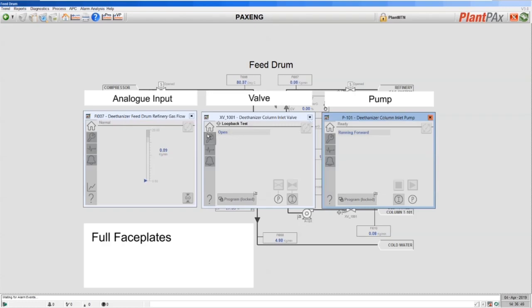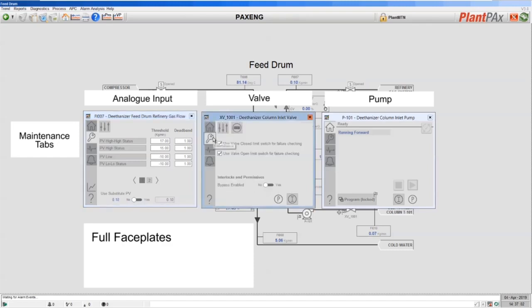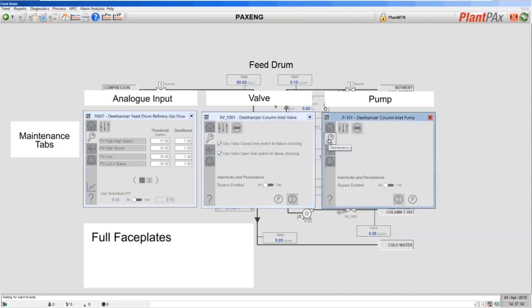The philosophy of the design for the full faceplates is that there is a tab for each logged-in role of a user. As an operator, I'll find most of what I need on the home tab that we're currently displaying. If I was a higher-level maintenance user, I would find most of what I need on the maintenance tab, where I can do things such as bypass interlocks.